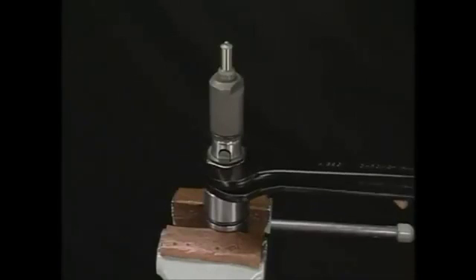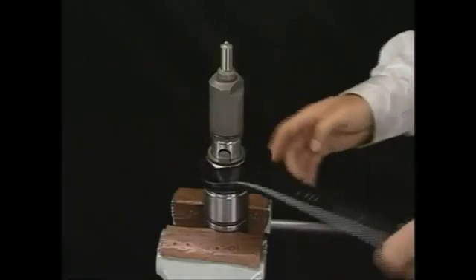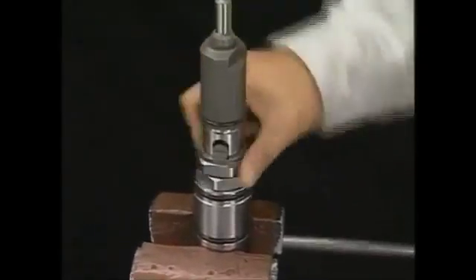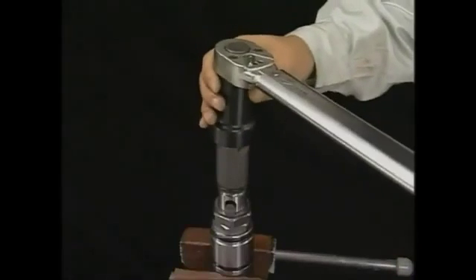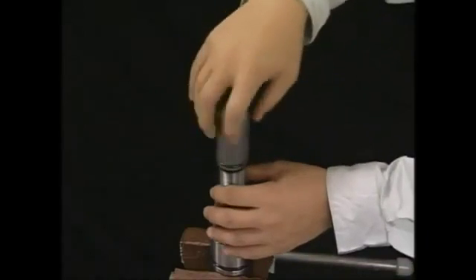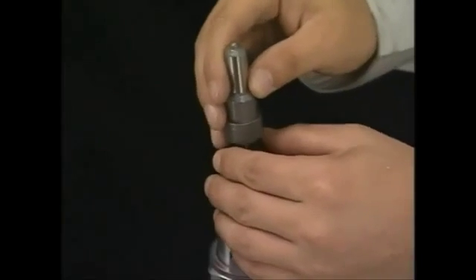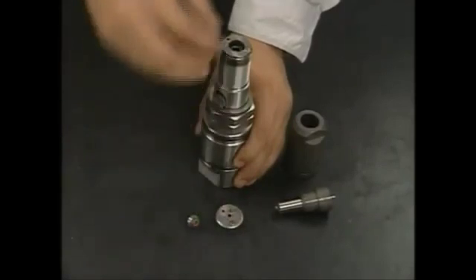Firstly, loosen the fuel injection pressure adjusting nut. Remove the nozzle case nut to remove the nozzle assembly. It is then possible to remove the spacer, spring seat, and spring hold from the fuel valve body.